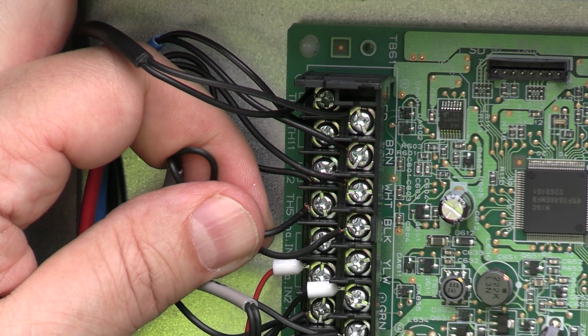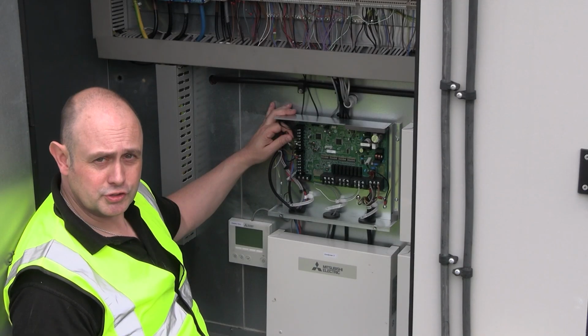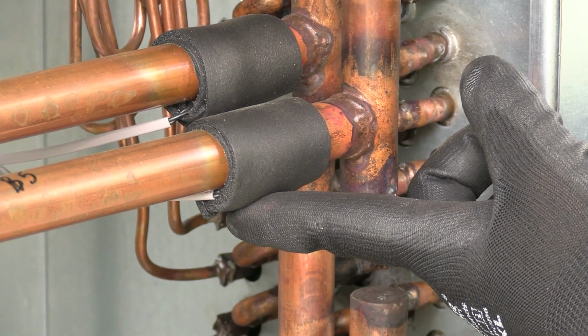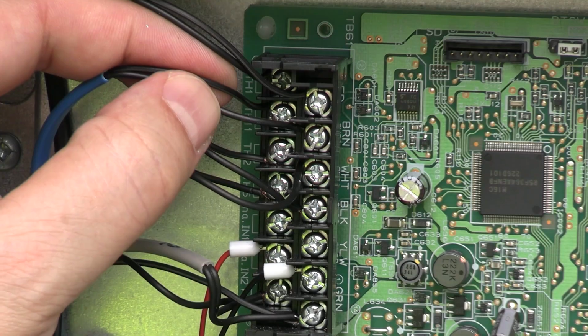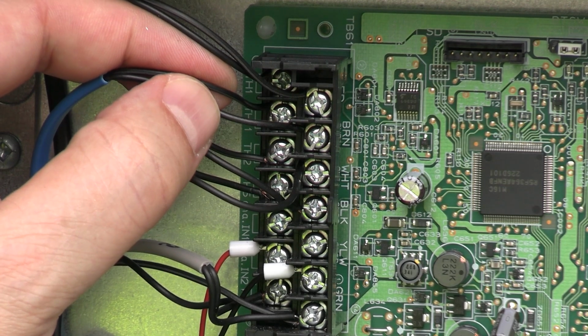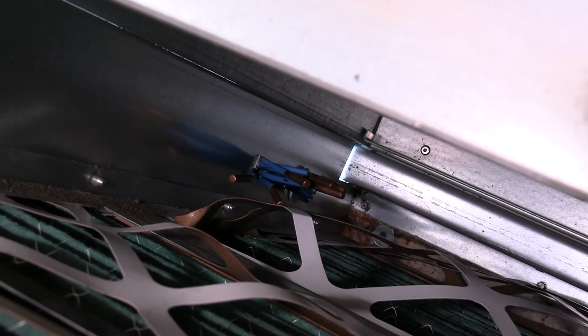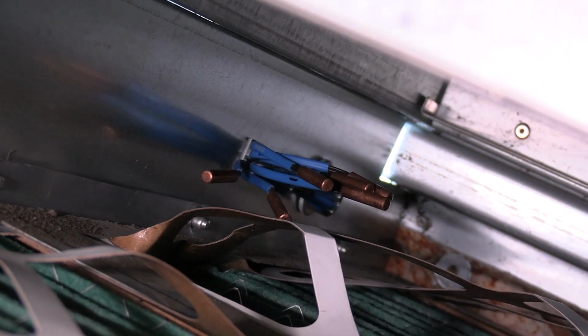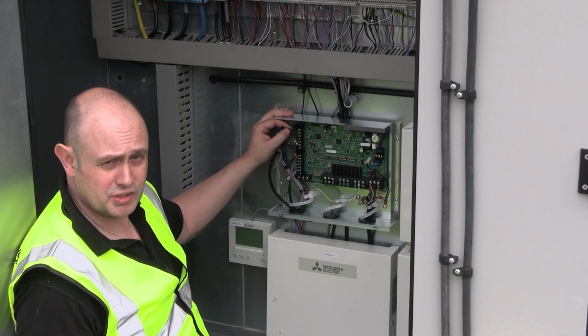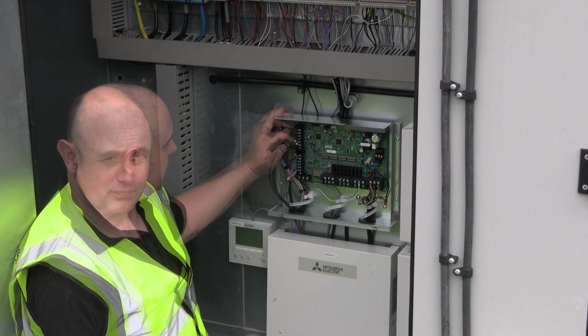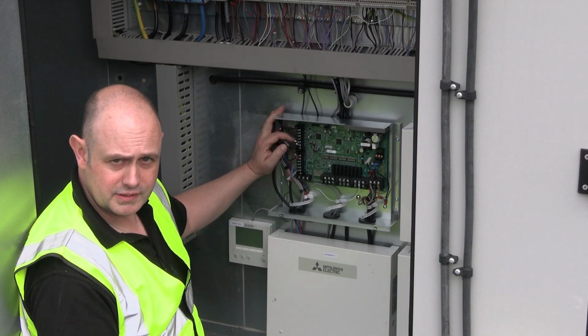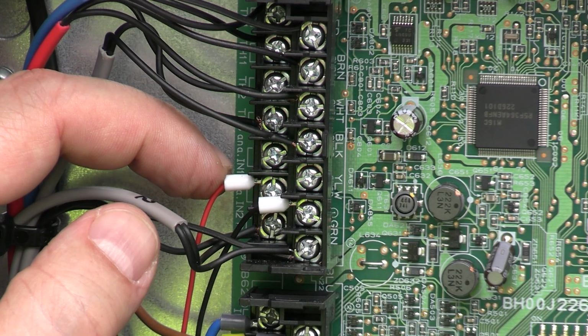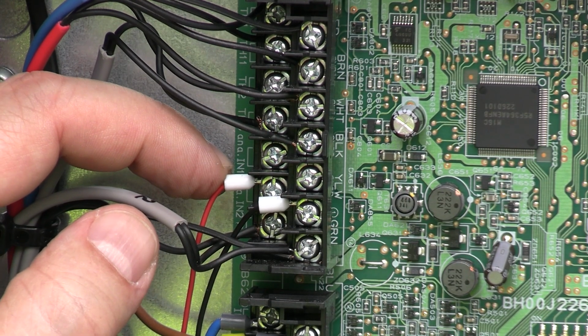TH5. So this is measuring the temperature of the refrigerant at the other end of the coil to make sure it's definitely done its job. TH11. So this is telling me what the heat exchanger inlet temperature is expecting to see. So it's telling me what the air temperature going onto the coil is. Connection onto TB61, connections 11 and 12. They've used this to control the overall duty.